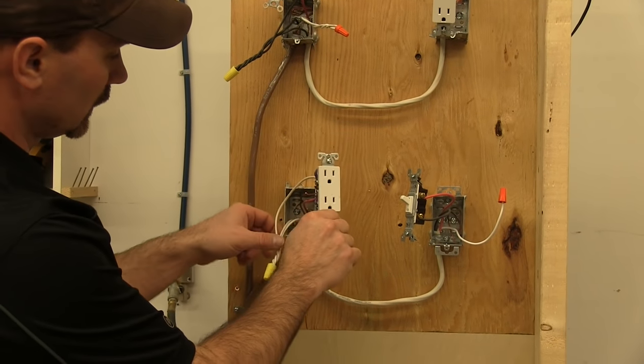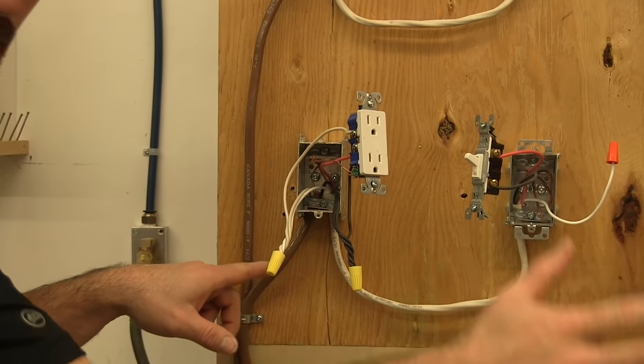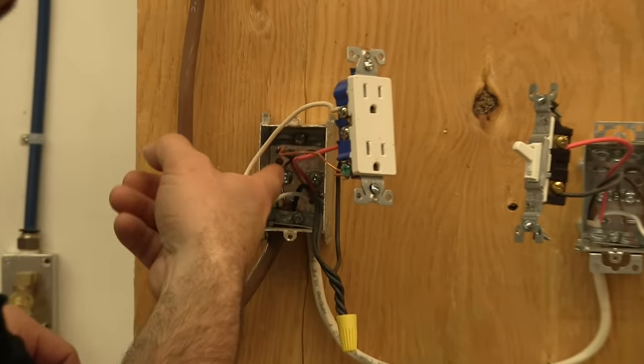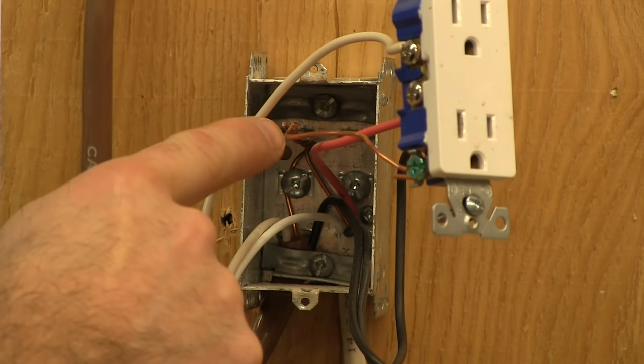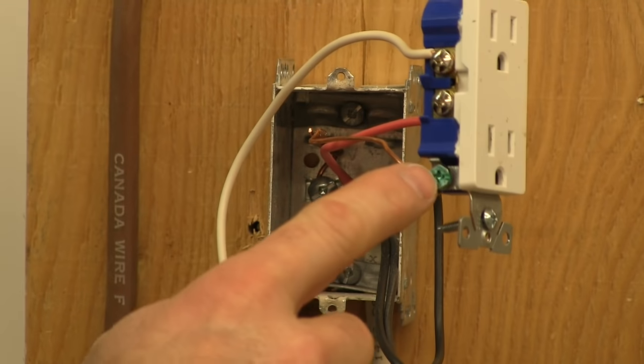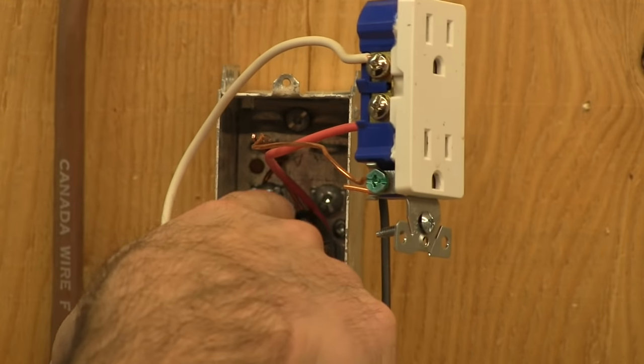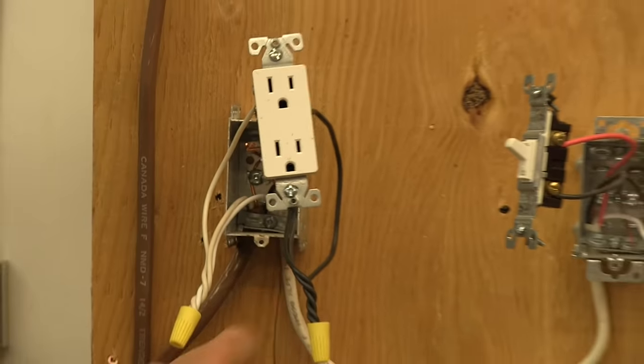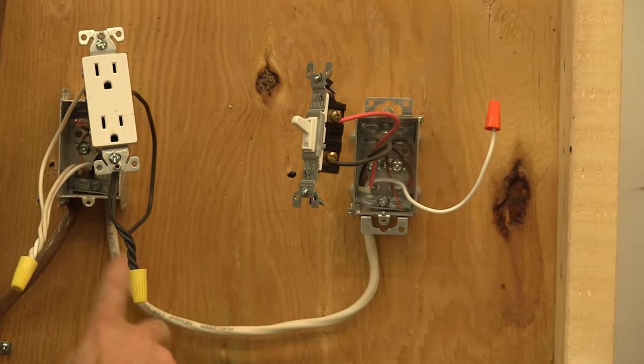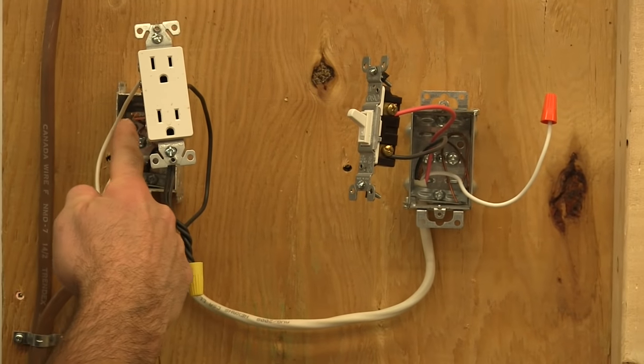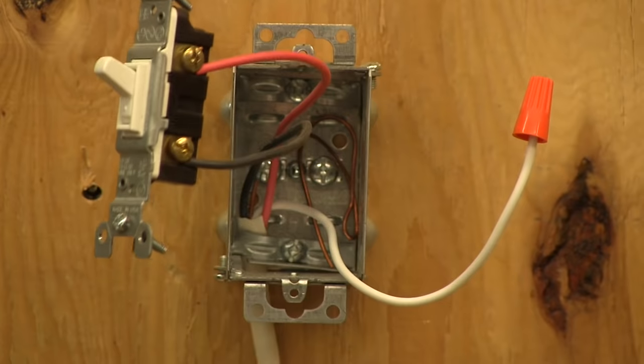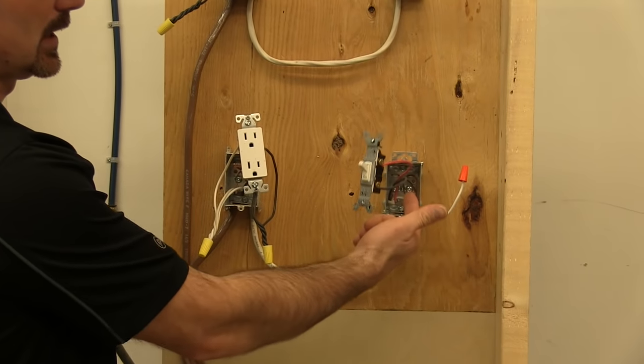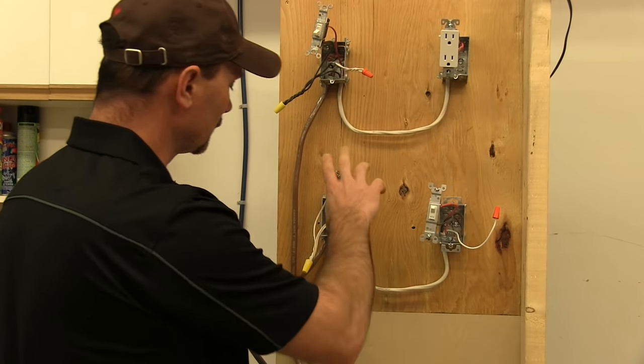So that's all pretty straightforward. As far as grounding goes, your ground will be grounded at the breaker box. It's coming in through your supply, it's twisted together with any other grounds coming into that box, as well as one that's feeding and grounding the receptacle itself, and it should be attached to the metal box in the back through a grounding screw. Same idea over here: there was a piece of ground wire in this cable that goes between the switch and the receptacle, so it's twisted together up here and hooked together, and it comes over and is simply grounded to the ground screw in the back of that box. If your area calls for grounding on the switch, then you would have another piece coming out and grounding the switch. So it all depends on your code.